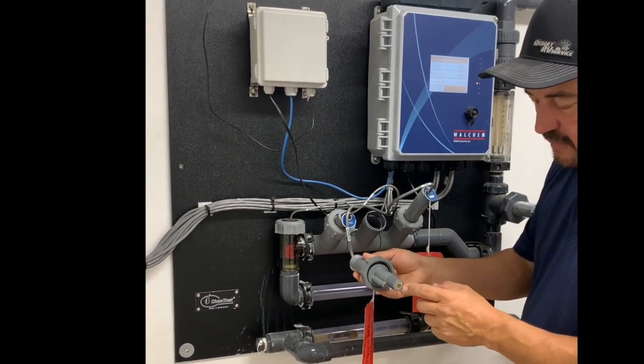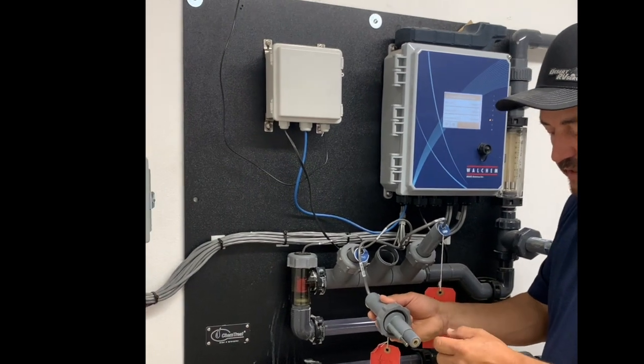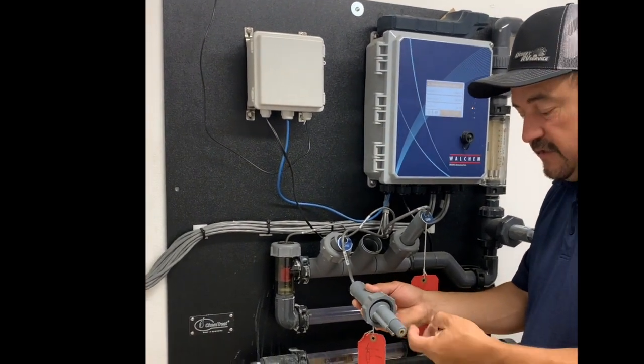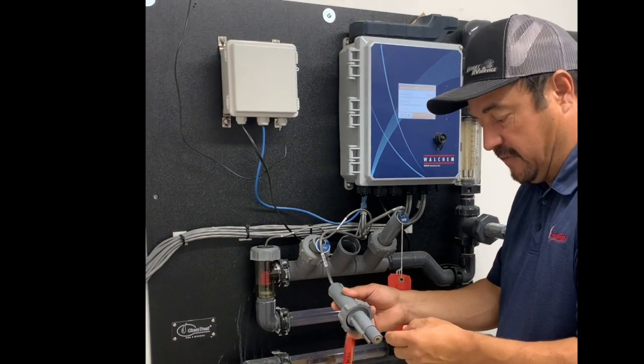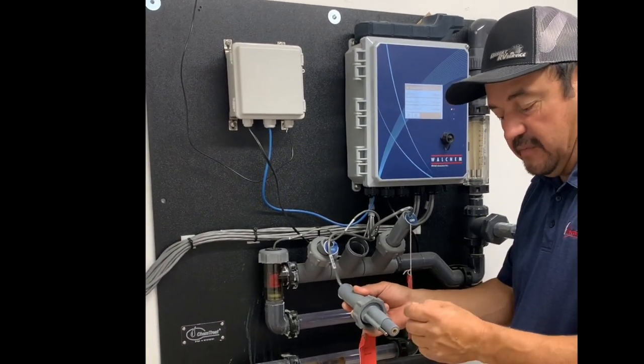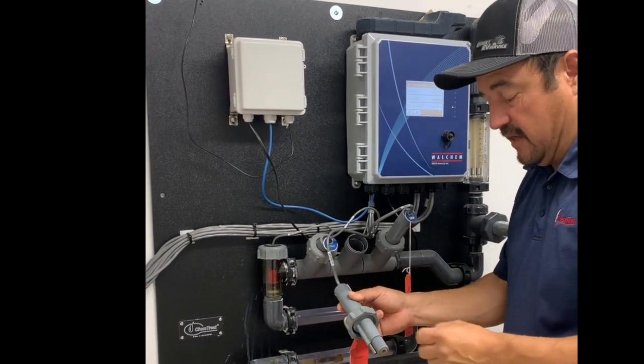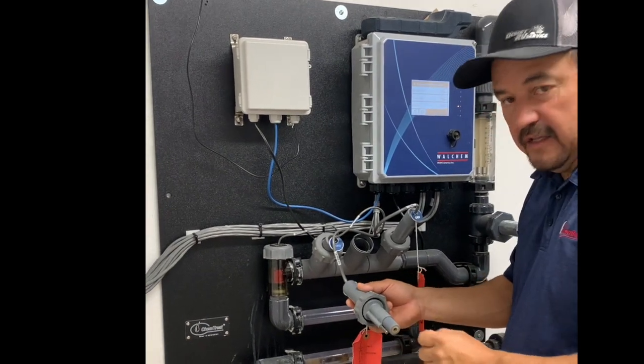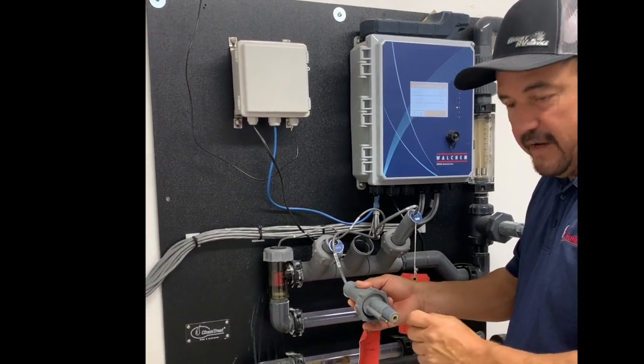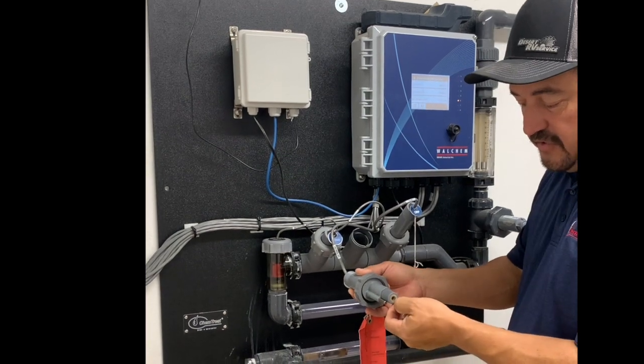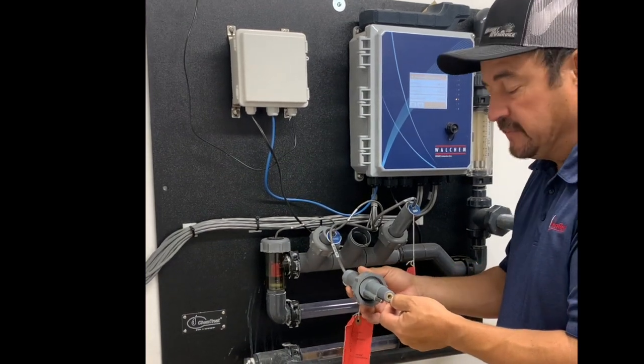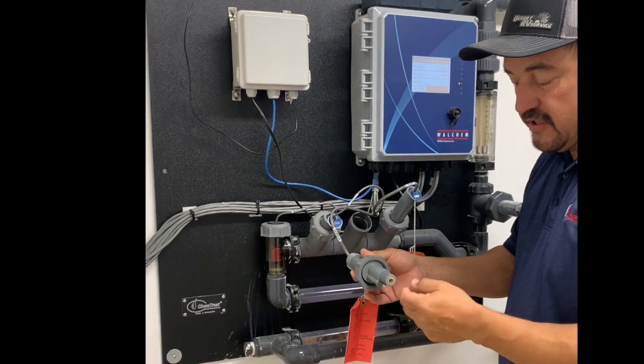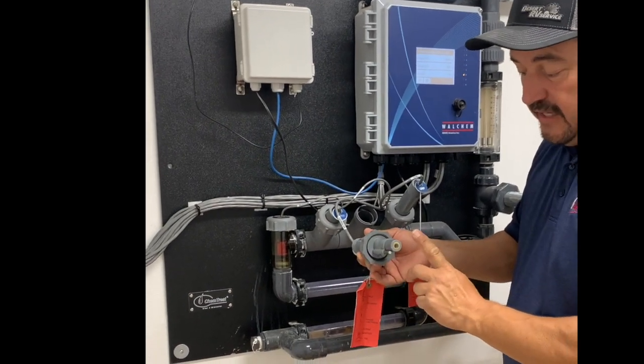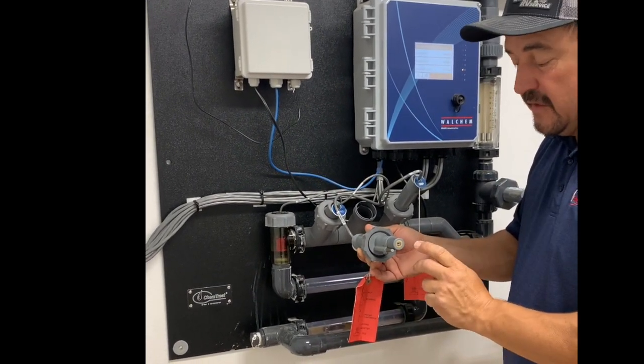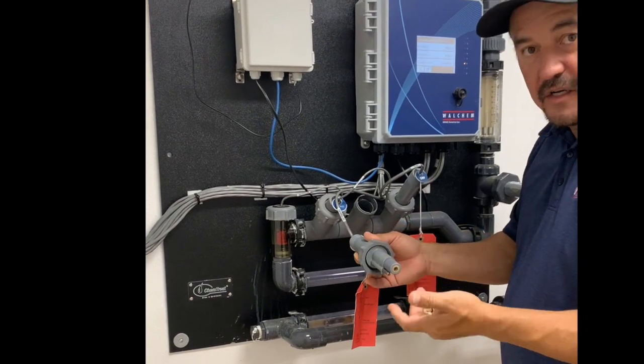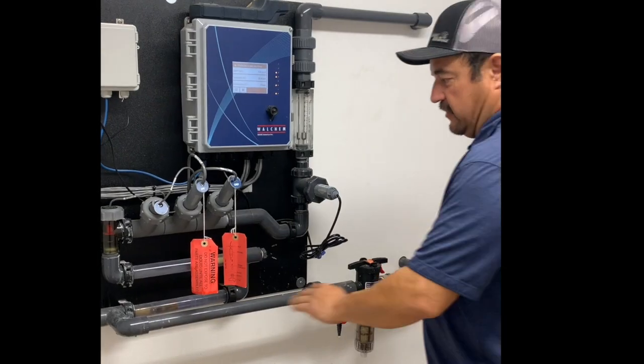So if you notice that there's something on there that you can't get off of there, you need to determine what it is. You know, if it's calcium carbonate, then you need to possibly do a 5% hydrochloric acid solution, and then you can get that off there. You don't ever want to scrape on that or scratch this lens. If you do, you're going to damage the lens. Also, you don't want to use any harsh detergents that will take the thin layer off of that lens. Once you've done that, you've damaged the lens and it's not going to read properly. So now we have flow back on our unit.